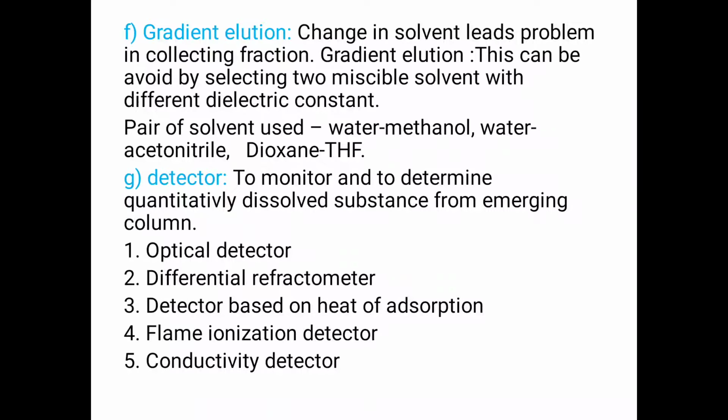These are suitable for ionized substances in aqueous solutions. The effluent is passed through the measuring cell of the detector, which contains two or three platinum electrodes within a Wheatstone bridge circuit and is operated by alternating current. So conductivity detectors are used for ionizable substances in aqueous solutions.